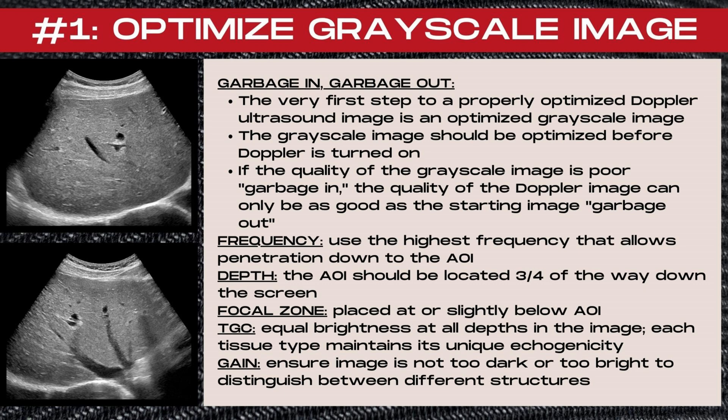If the quality of the grayscale image is poor — garbage in — then the quality of the Doppler image can only be as good as the starting image — garbage out! To optimize your grayscale image, first look at your frequency. You want to use the highest frequency that allows penetration down through to your area of interest.